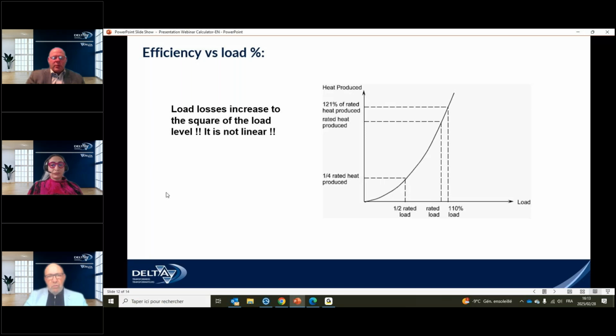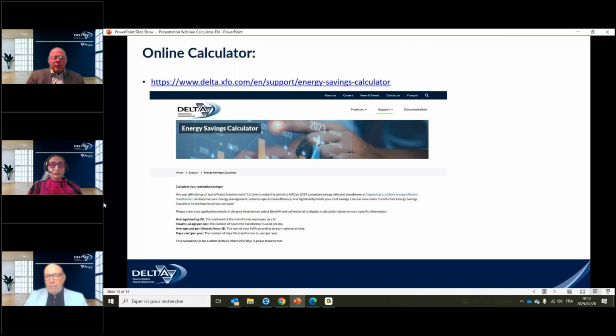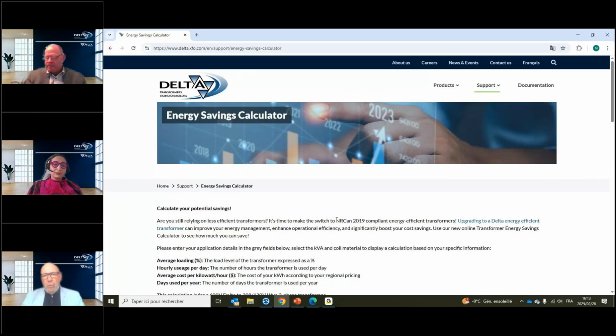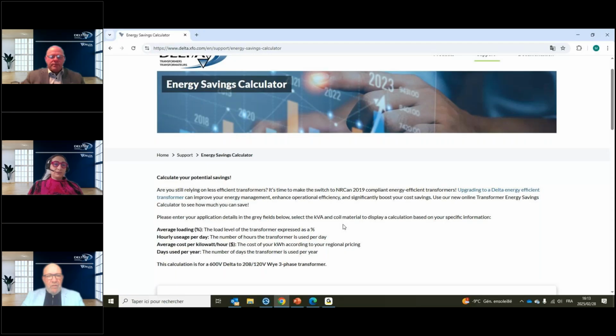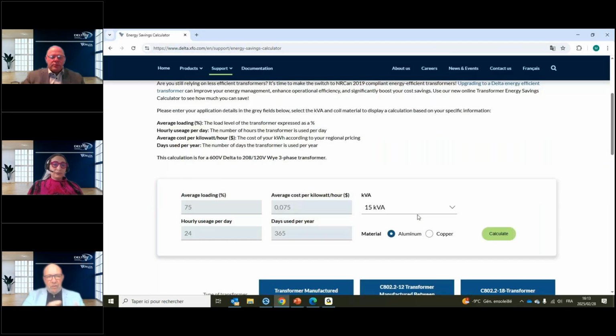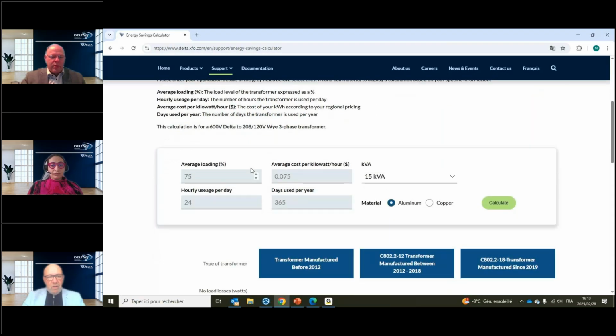So this is where our tool comes into play. That being said, I'm going to jump here on our website. Out of the support section of our website, we have our new energy saving calculator. This is made for transformers with 600 volt primary and 120/208 secondary, from 15 kVA to 300 kVA, which is probably 85% of the transformers out there in the marketplace, installed in all buildings. With just some very simple data, you will get the information. So I'll run a quick one here.